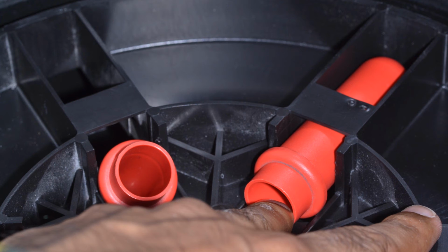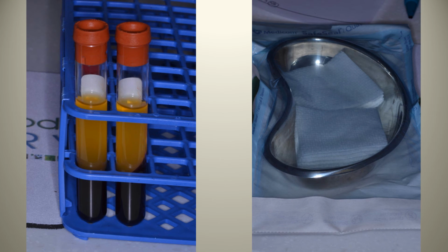However, there haven't been any studies that have satisfied me that there is a difference between any of these. Once this process has been completed, you can see in the picture on the left that the bottle has a yellow layer which is more flat, and the bottle on the right has a 45-degree angle. That's the difference between using the horizontal centrifugation unit or the centrifuge with the 45-degree angle.